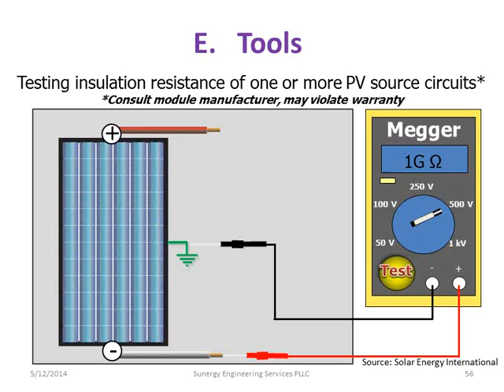And the other thing to bring up with insulation resistance is it's not always the same. It's kind of a moving target. It's very dependent on the temperature and on the humidity when you do the testing. So a lot of times people use insulation resistance testers to track down a fault. There's a ground fault, the inverter keeps on clicking off, and they try to find out where it is. And that's a good tool to try to track that down, but sometimes it's only faulting like when it rains or when it's really high humidity, so you actually have to sprinkle down the system to try to find where the short is, which isn't that much fun to do. But it is very dependent on that.